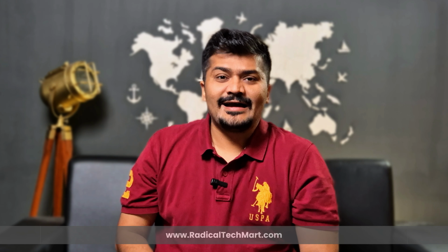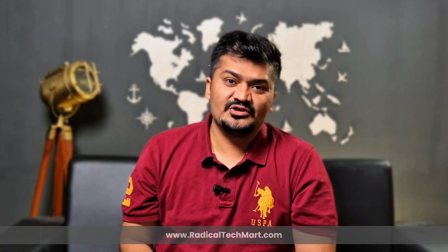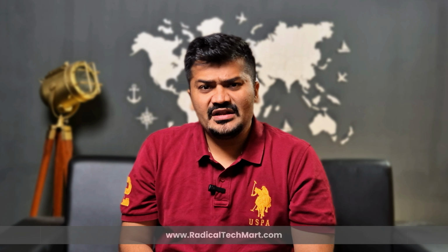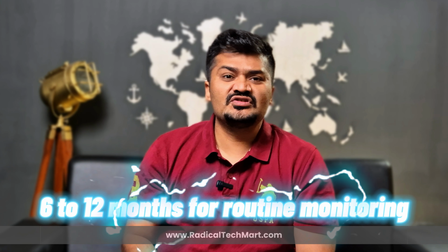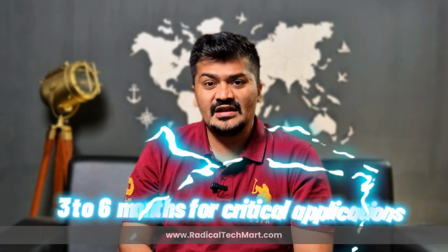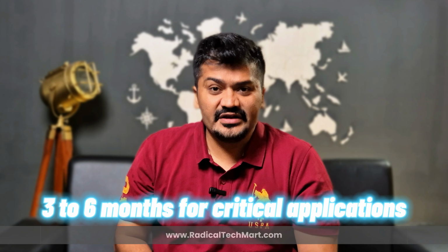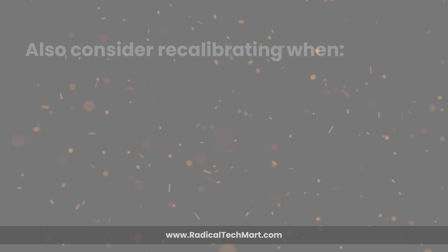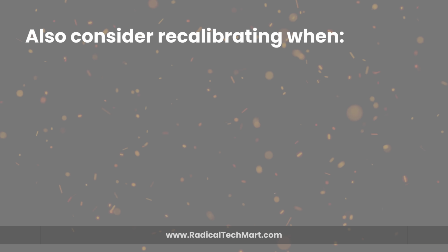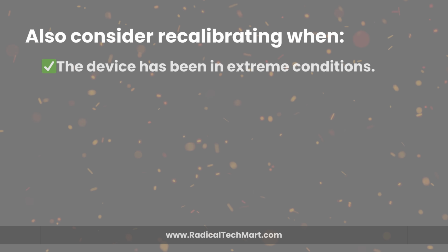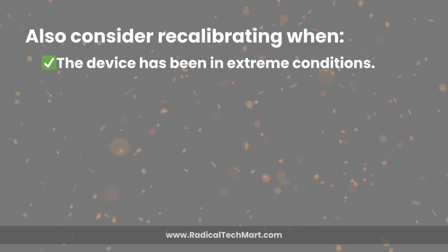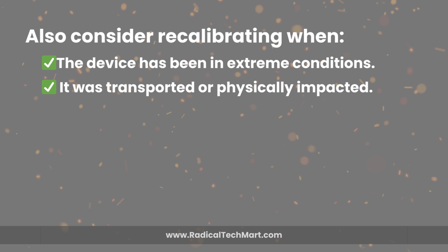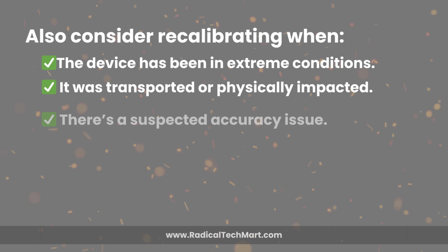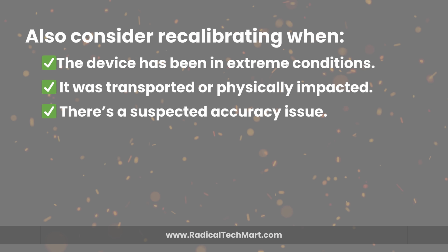Now let's check how often you should calibrate your humidity sensor. The general recommendation is every 6 to 12 months for routine monitoring and every 3 to 6 months for critical applications. Also, consider recalibrating when the device has been in extreme conditions, was transported or physically impacted, or there is a suspected accuracy issue.